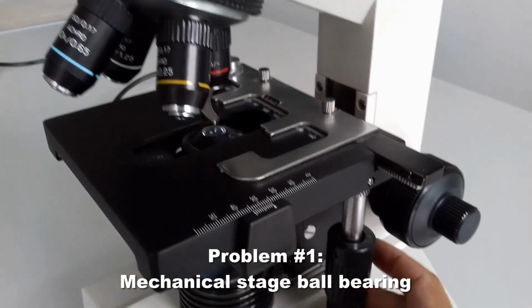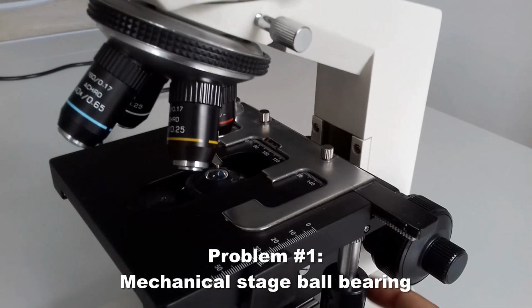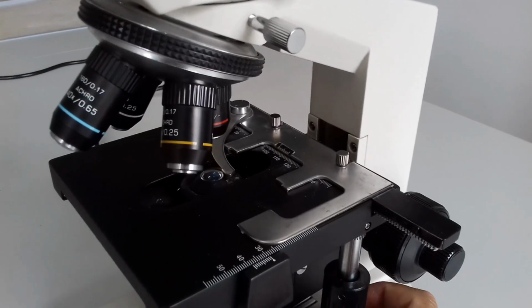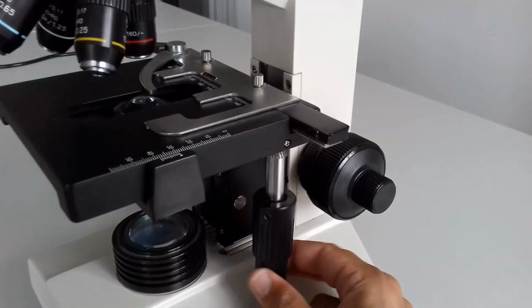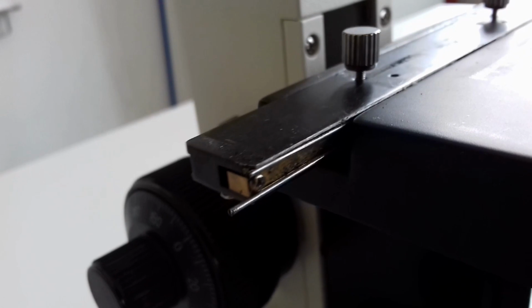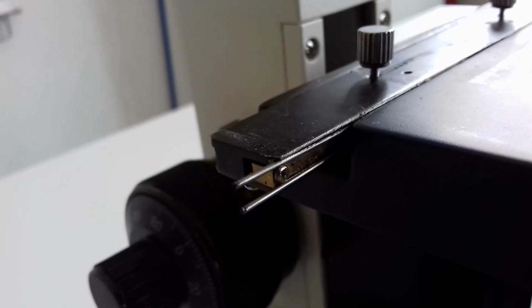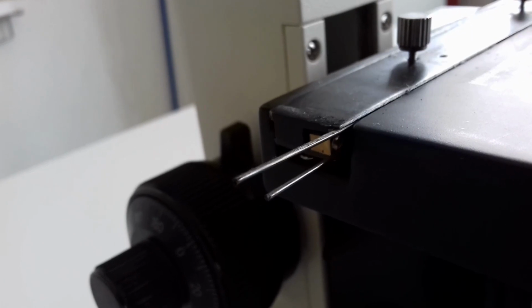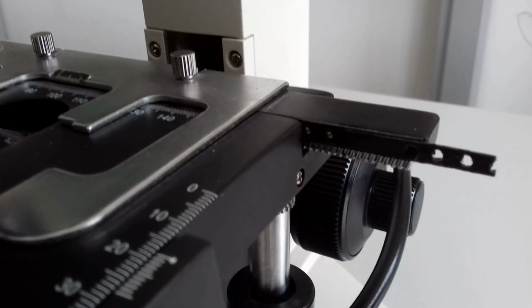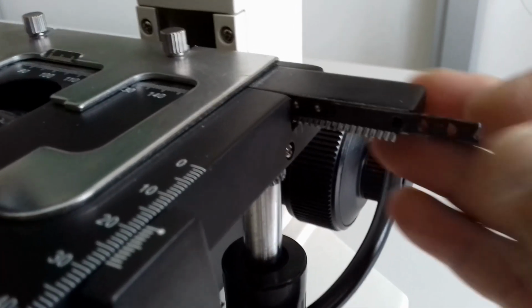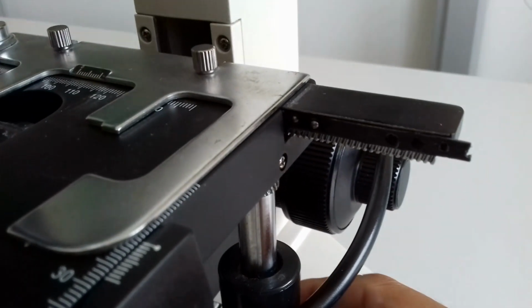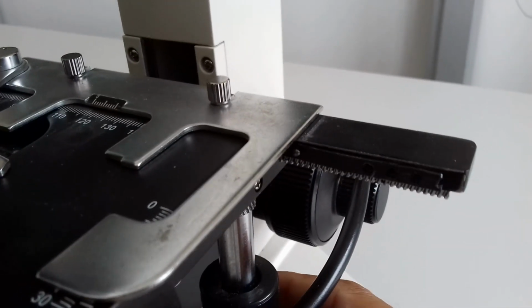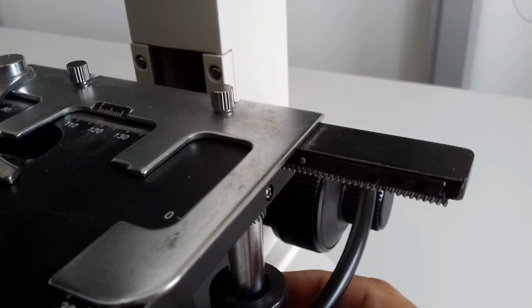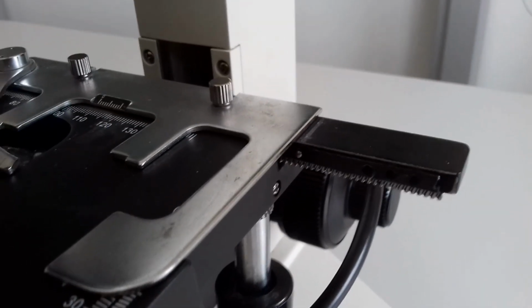So, number one, I tried to move the mechanical stage of one microscope and I heard a scratching sound. So there was a problem here, and I found it very quickly because on the left side you could see two wires coming out because the ball bearing of the mechanical stage broke. You can also see there's a problem here on the right side, on the other side of the stage. Apparently some screws got loose and we were not able to retain the guiding wires that held the steel balls that made the slide operate smoothly.